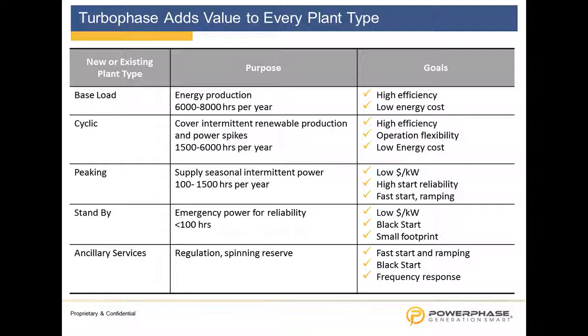A direct example would be to put 50 megawatts of Turbophase into your F-class combined cycle power station, having it there on standby, starts in 1 minute, and provides 50 megawatts in 1 minute at combined cycle efficiencies, instead of starting that LM6000 or that SGT 800 or something of that nature in less than 8 to 10 minutes, and having the start costs and the start emissions associated with starting that unit, and then also having to build that peaking power plant to begin with. So we can basically directly offset those peaking power stations.